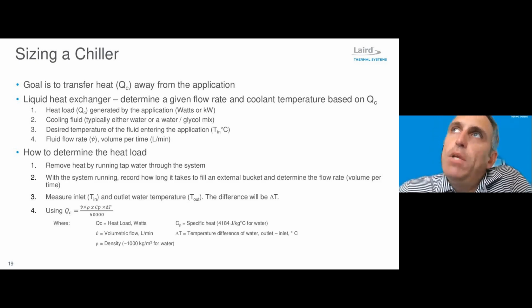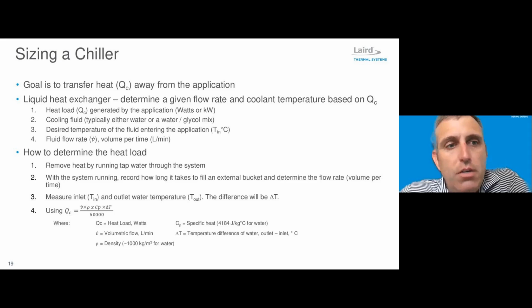So if heat load's going up and we're trying to maintain the temperature rise constant, then we need to increase the flow rate. And so typically, using imperial units, well, kind of a mix, I guess, for every kilowatt of heat, it tends to be about a gallon a minute, so 4 liters per minute or so. And so as those heat loads get higher, a 4 kilowatt system would use around 4 gallons a minute or 15 liters per minute or somewhere in that range. But we need to keep in mind the pressures associated with those higher flows, as I discussed also, right? So when we get into higher flow rates, this requires larger tubes and heat exchangers that have lower pressure drops in order to accommodate those higher flows.